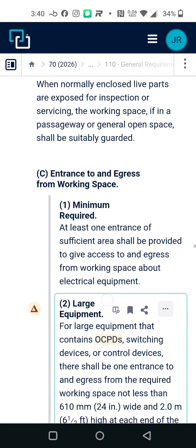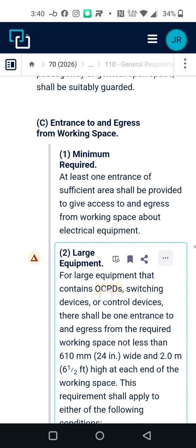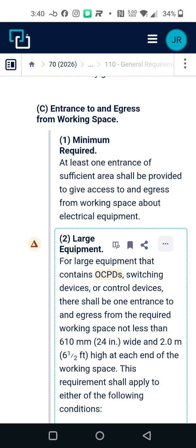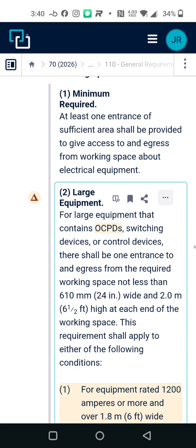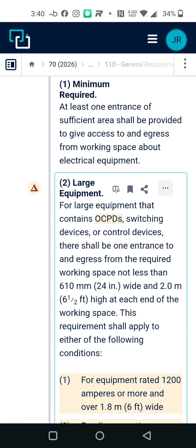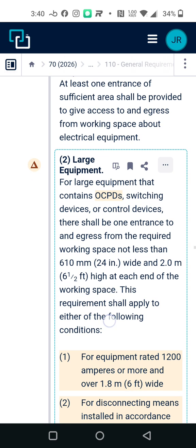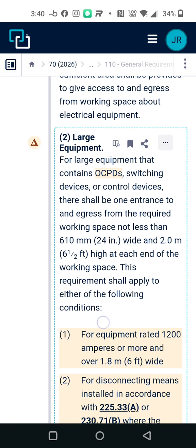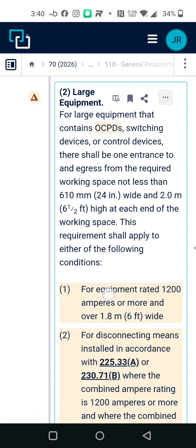Entrance to and egress from working space. Minimum required: at least one entrance of sufficient area should be provided to give access to and egress from the working space of electrical equipment. Large equipment. For large equipment that contains overcurrent protective devices, switching devices, or control devices, there should be one entrance to and egress from the required working space not less than 24 inches wide and 6 1/2 feet high at each end of the working space.